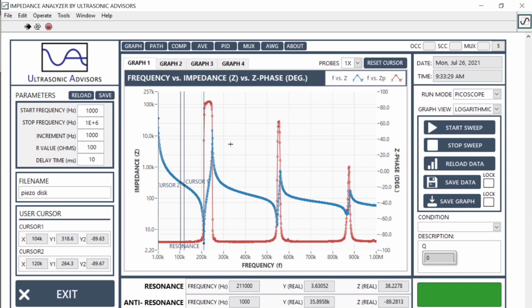They're not for a bar. These would be exactly, they would be in exact intervals. However, for a radial mode, there are other distinctions which cause it to be not precisely 3 times higher than the original resonance frequency, but nonetheless, we can analyze it. So the procedure for characterizing a disc or a bare piezo element is different than for a transducer, although you can analyze them in the same way. But in order to extract theoretical properties, like the material coupling coefficient of the radial mode, or the elastic compliance properties, also the piezoelectric charge coefficient D31, you'll need to apply other equations to the measured resonance frequencies.